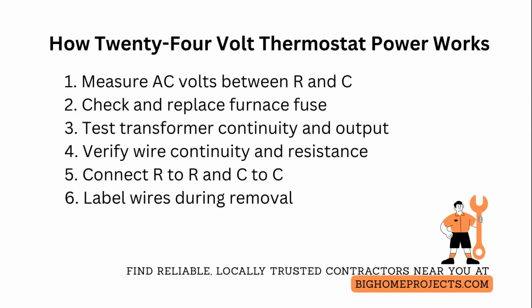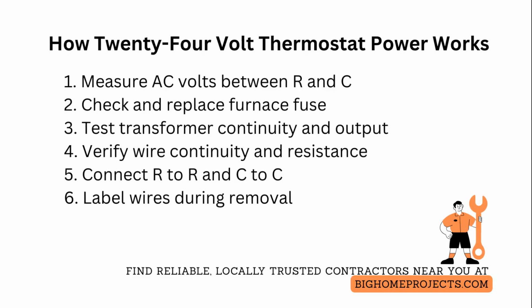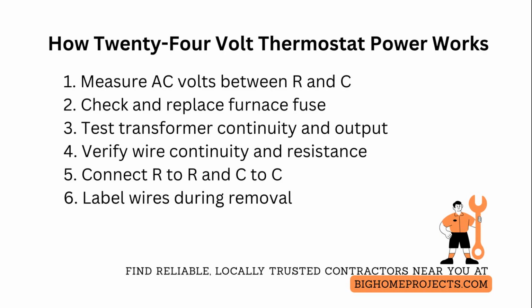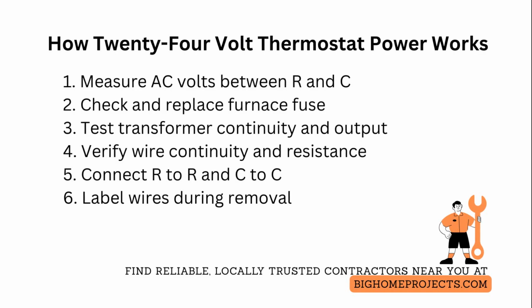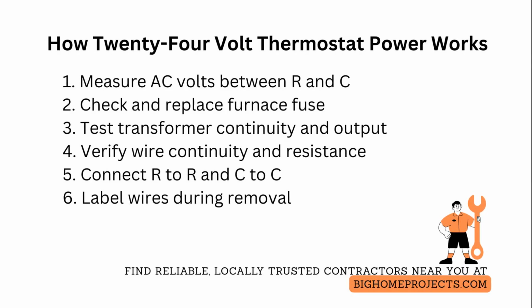If the reading is low or zero, check for a blown fuse on the furnace control board. Most boards use a 3 to 5 amp fast blow fuse located near the transformer, and replace only with the exact type stamped on the board. Inspect the transformer secondary for continuity and proper output. A shorted or overheated transformer will show an open or drastically reduced voltage and should be replaced with a matching voltage and VA rating to avoid overloading.